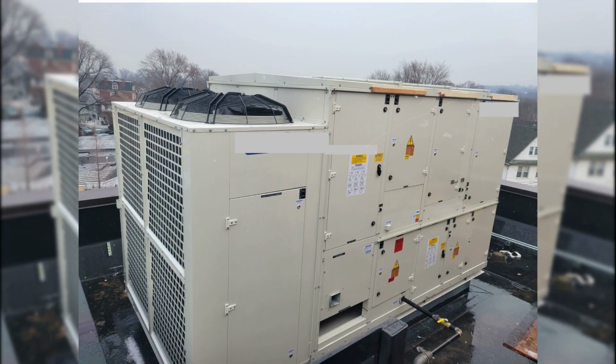22. For A2L refrigerant systems, continuous monitoring is required if a refrigerant leak could exceed the 25% lower flammability limit, LFL, in the event of a ventilation system failure. This may require area refrigerant leak detectors.